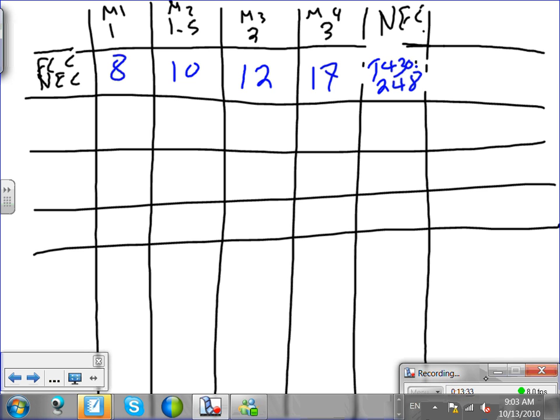Okay, so NEC, table 430.248. Everybody knows how to use this table, guys? The voltage in this table says 230. So, Muhammad, my friend, you're going to be confused now. You're going to say, well, Chad, there's no 240. If you look at the top of the voltage, it says 220 all the way to 240. You're going to use 230. For the range between 220 and 240, you use the amps of 230. Okay? Everybody got that? All right. You guys are cool.